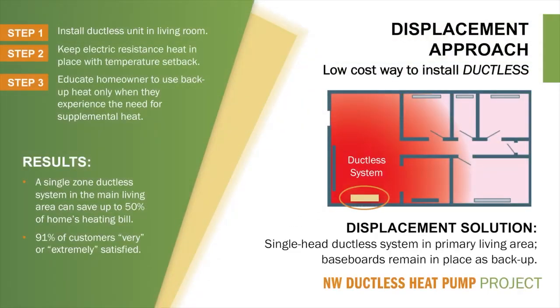One way to make ductless heat pumps viable for cold climates involves how it's applied. In a method called displacement, the existing heating system remains in place and operates only as needed. Displacement works especially well in homes with electric resistance heating, because it saves a lot of energy and improves occupant comfort. It's worth noting that displacement of other types of heating by use of a ductless heat pump works well too.